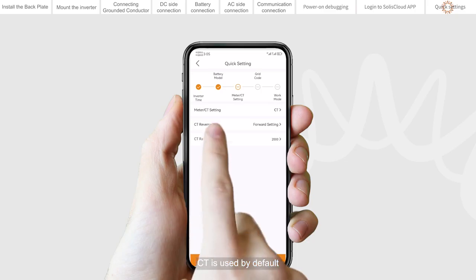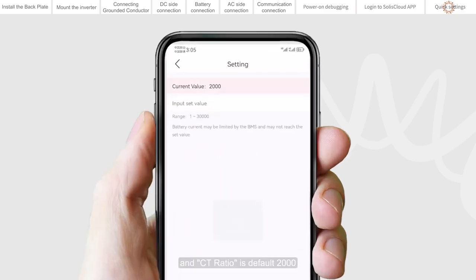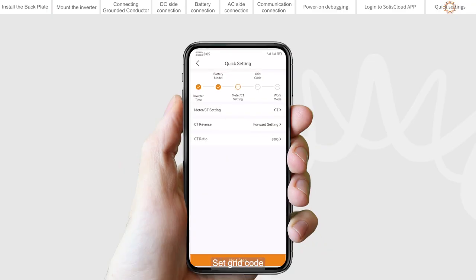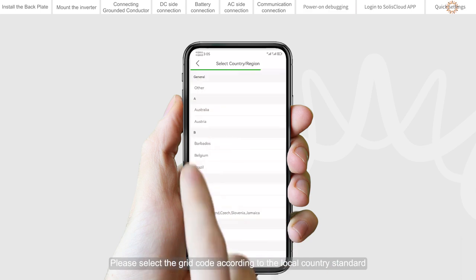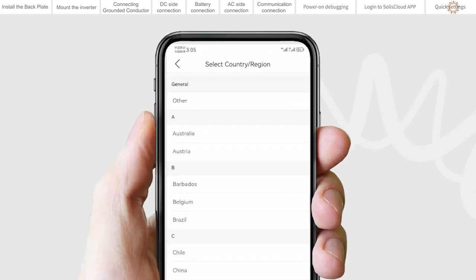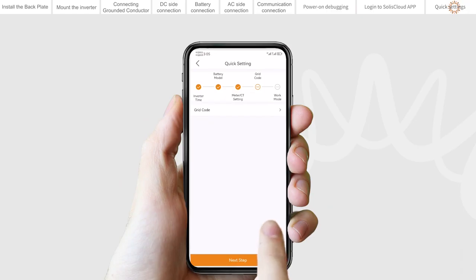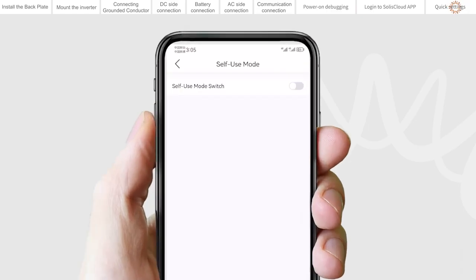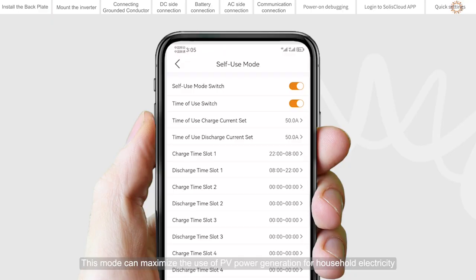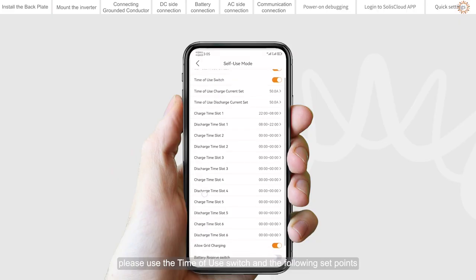CT is used by default, and CT ratio is default 2000. Set grid code. Please select the grid code according to the local country standard. Set the work mode. Recommended setting is self-use mode. This mode can maximize the use of PV power generation for household electricity, or store it in batteries and use it for household electricity. If you need to manually control the battery charging and discharging with respect to time, please use the time of use switch and the following set points.